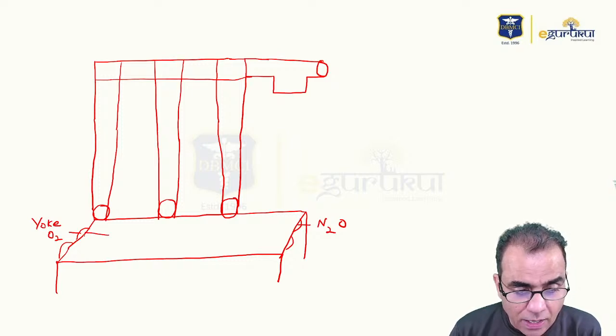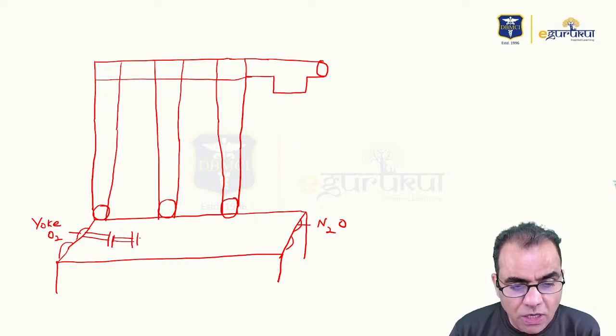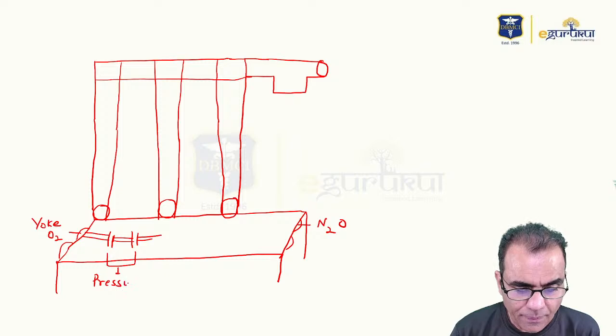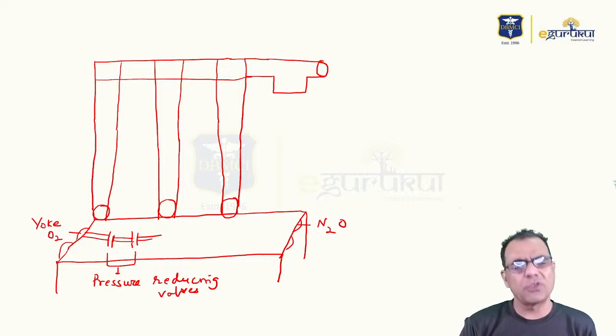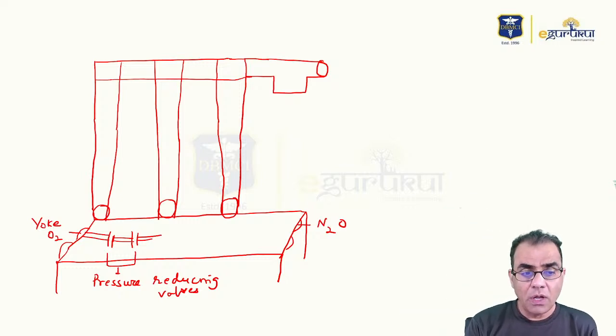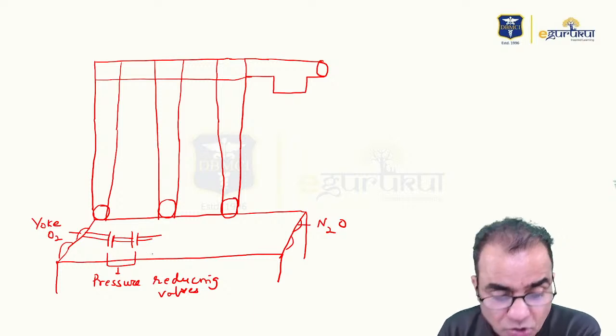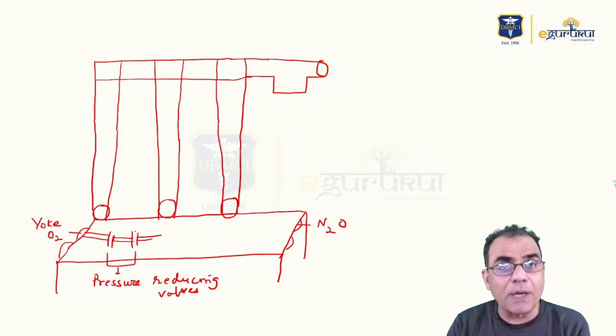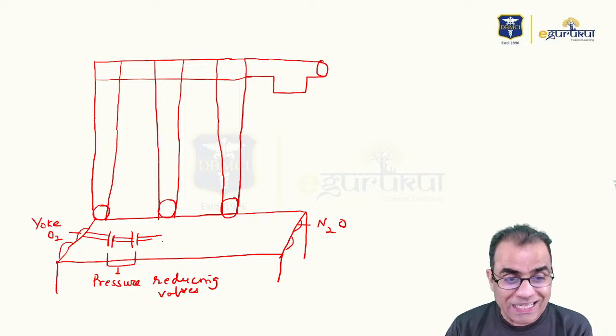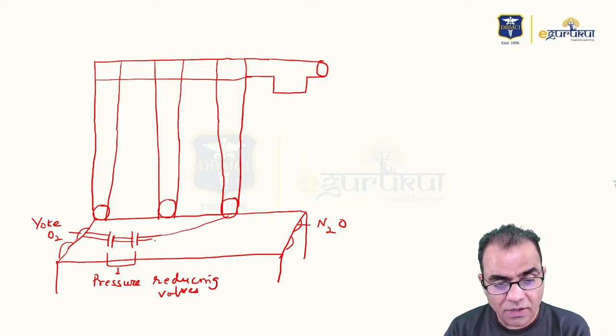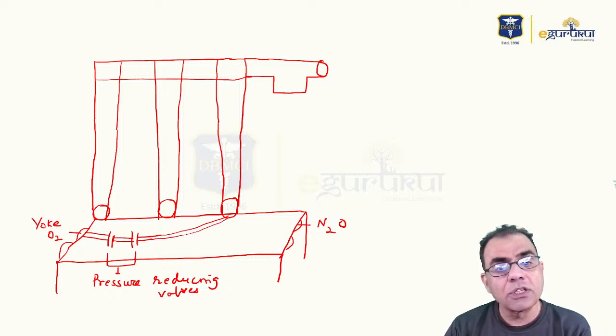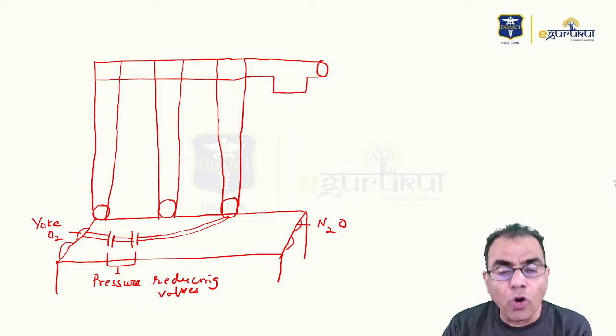So such high pressure is obviously not acceptable. So here there are pressure reducing valves. Now, how much pressure is reduced by each valve? There are two valves, so those details, of course, are not required for you. They don't ask that much detail from you. But you have to remember that pressure has to be reduced drastically. Otherwise, even that can burst your anesthesia machine pipes. So pressure is reduced drastically, and after that much pressure reduction, this oxygen will pass through its flow meter tube.